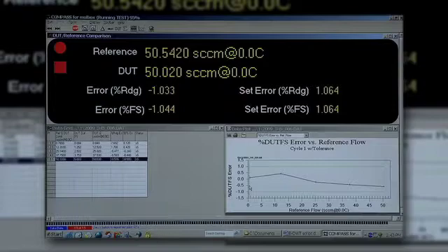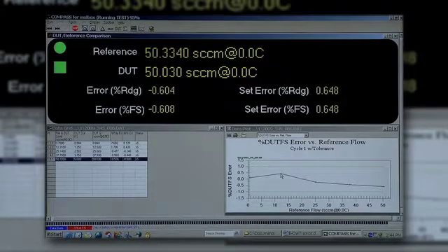Okay, there's our 5th data point, and we have adjusted it within tolerance. So we've successfully made adjustment to the MFC.